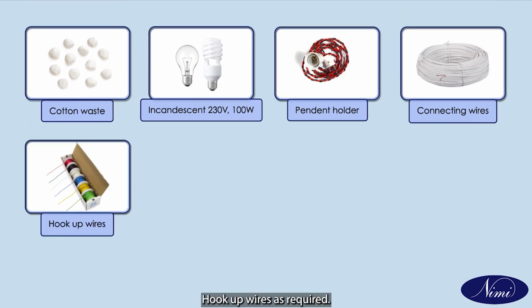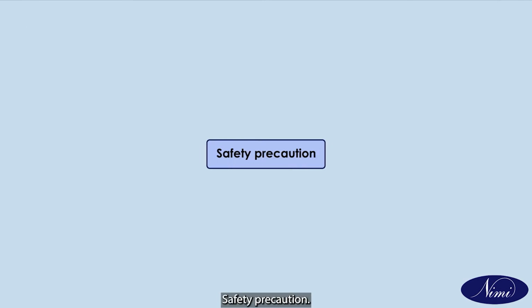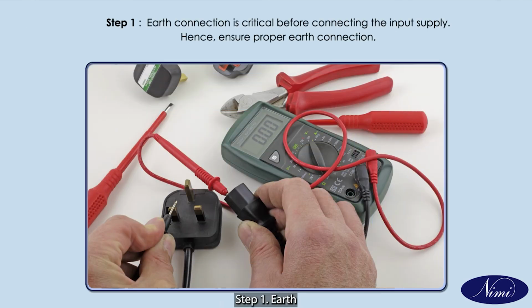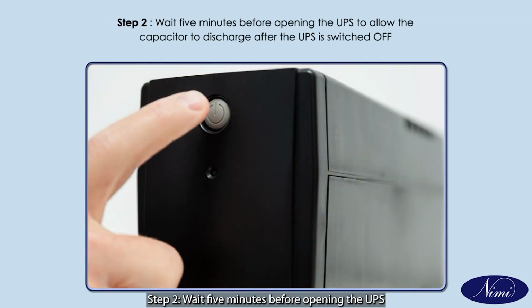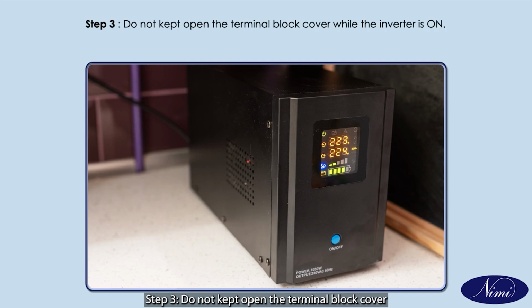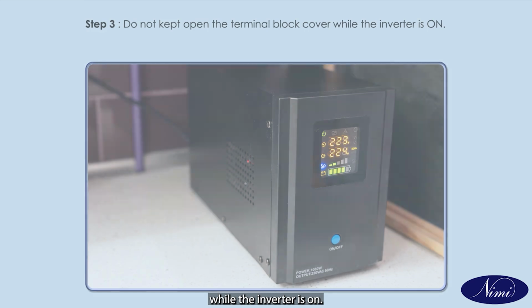Hookup wires as required. Safety precaution. Step 1. Earth connection is critical before connecting the input supply. Hence, ensure proper earth connection. Step 2. Wait 5 minutes before opening the UPS to allow the capacitor to discharge after the UPS is switched off. Step 3. Do not keep open the terminal block cover while the inverter is on.